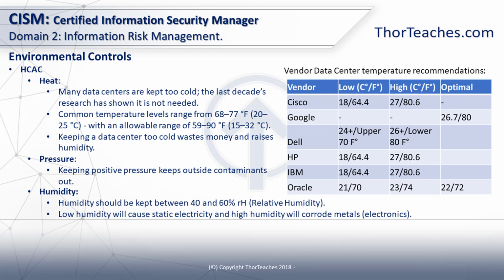And of course our HVAC should be spec'd to handle not just the heating and the air conditioning, but the humidity as well. If one of our ACs breaks, can the last one or the other two handle the load? I've worked in data centers both where it's really dry, so we actually had to use the humidifier, and places where it's really humid, and we had to use the dehumidifier. So in your due diligence, figure out what the area you're in or the data center you're building is, and ensure that equipment can handle that environment.